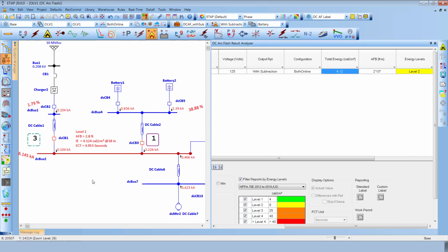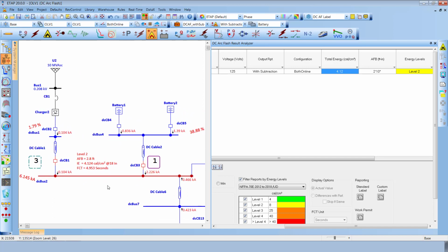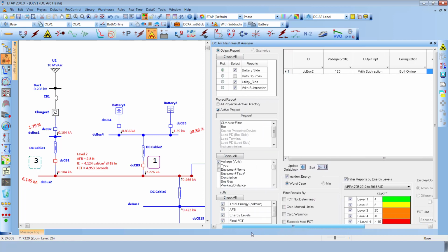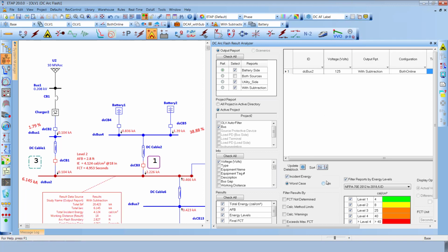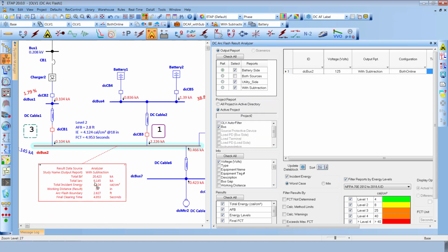And once the worst case scenario is achieved based on the both online configuration, ETAP has the capability to display the worst case incident energy in the ETAP one-line diagram with the help of data blocks, which is introduced in ETAP 20 version. To show the one-line diagram with the worst case incident energy from the arc flash analyzer, simply go to the update data block option and enable the data block toolbar in the one line diagram, so that the moment you hit the update data block toolbar, the incident energy gets updated for the worst case based on the selected reports from the arc flash analyzer.